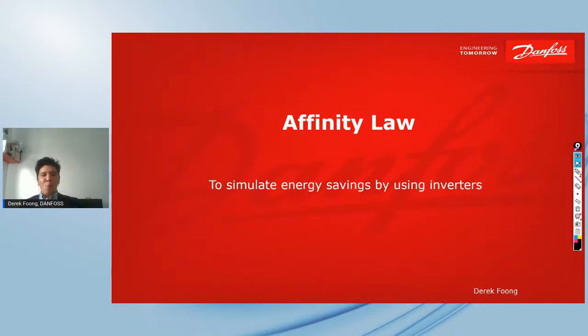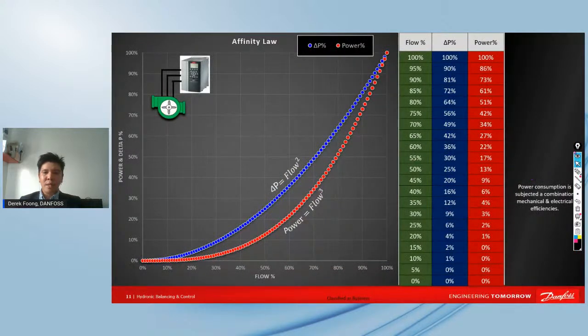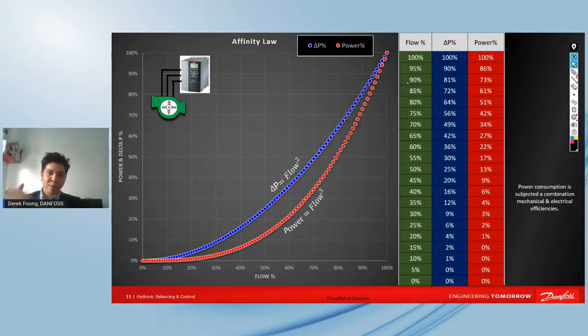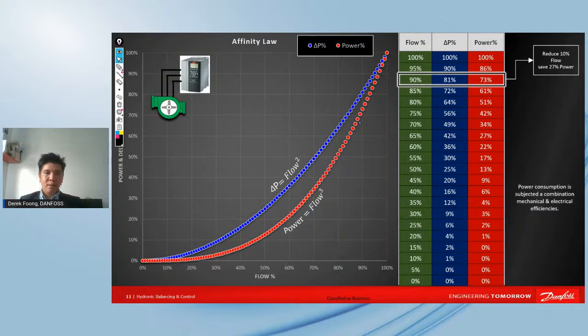Of course, this is one of the number one reasons we know that inverters, if you couple them with pumps or fans, especially centrifugal pumps or fans, respect the affinity law. The intention of this slide is to simulate the energy savings in the curve. We all know that if we tune the inverter and reduce the flow rate by 10%, the end result is that we save about 27% of the energy. At the same time, if we reduce the flow rate down to 80%, we save power by around 49%.